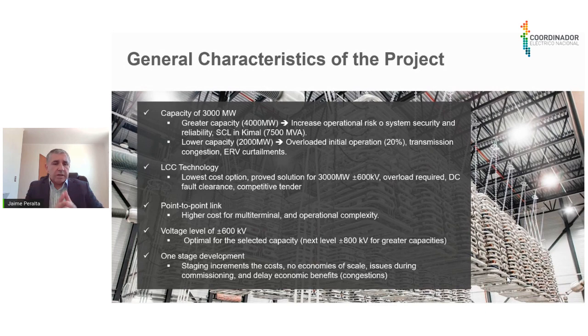Well, voltage level comes from the decree from the Ministry of Energy. It was at least 600 kV, and after the studies that we conducted, we estimated that 600 is the optimal voltage level. Moving to the next level, like 800, is really for much greater capacities. And staging, basically, because of the loading that this line is going to have by 2029, it's going to reach its maximum capacity in 3 to 5 years. So basically, staging is not justified. We lose all the economies of scale, and we also introduce complexities during the commissioning of the projects in the second stage, basically delaying all the economic benefits of the project.